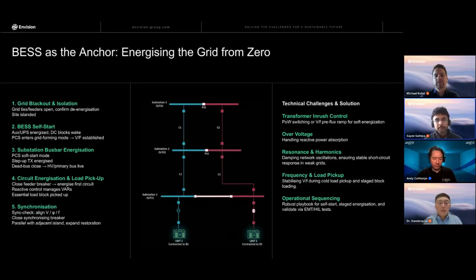During the black start, we will engage the battery racks to provide the DC voltage to charge the DC bus on the PCS. We are going to start the PCS in a soft energization or soft start mode, and then we energize the transformers and energize the dead bus. Once we energize part of the network's transmission system, we start engaging the load breakers, and then you would need the PCS to respond to the voltage and frequency fluctuations depending on the load blocks.